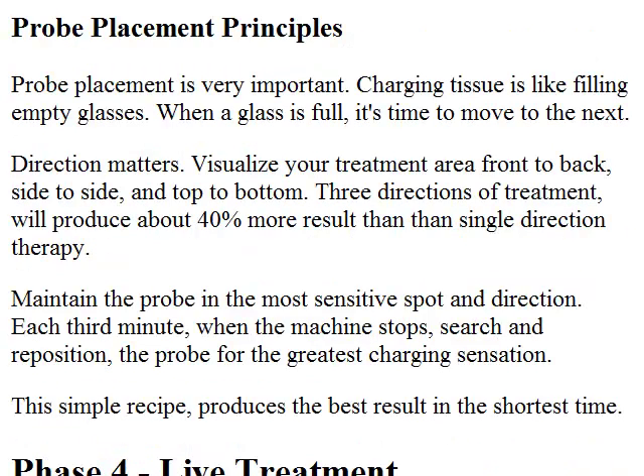Probe placement is very important. Charging your tissue is like filling an empty glass. When a glass is full, it's time to move to the next. Direction matters. Visualize your treatment area from front to back, side to side, and top to bottom. 3 directions of treatment will produce about 40% more result than a single direction therapy. Maintain the probe in the most sensitive spot and direction. Each third minute when the machine stops, search and reposition the probe for the greatest charging sensation. This simple recipe produces the best result in the shortest time.